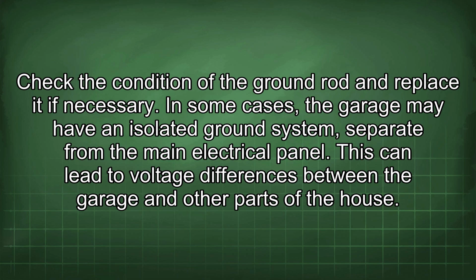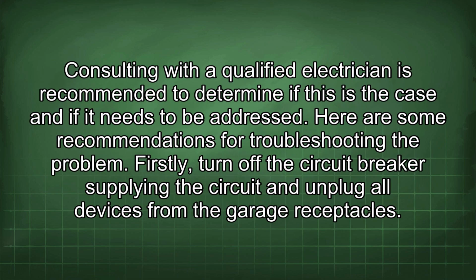In some cases, the garage may have an isolated ground system separate from the main electrical panel. This can lead to voltage differences between the garage and other parts of the house. Consulting with a qualified electrician is recommended to determine if this is the case and if it needs to be addressed. Here are some recommendations for troubleshooting the problem.